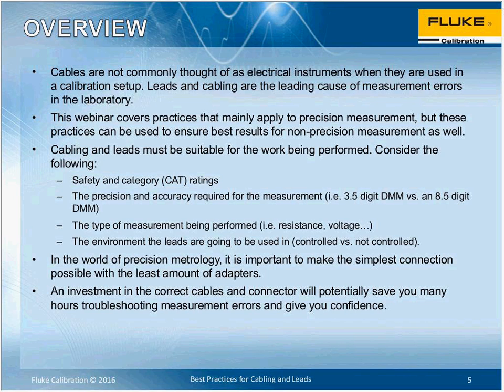One of the things that always comes up when we visit a customer is questions on cables and leads. A lot of the times we walk into a laboratory and the first question they have is they want to talk about a potential problem with the type of measurement, such as, hey, we're making this high resistance measurement, but we can't get the measurement to stabilize. Is there something wrong with the product? And nine times out of ten, you can walk over there and just evaluate the cabling situation, and within a couple of minutes have it solved.